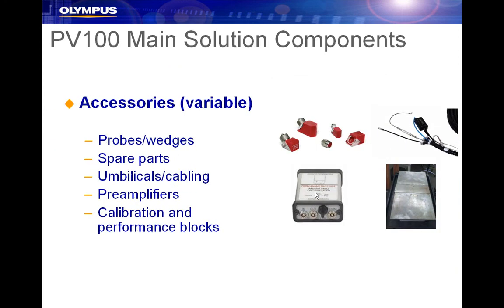Depending on the customer's needs, there are a lot of smaller components that typically go into a PV100 solution as well, including cabling, probes, wedges, spare parts, etc. All necessary components can be identified based on the welds to be inspected, so a total solution package is offered. If needs change, other accessories can be added later. Umbilical or divisible cable style wiring is typically used to group all the necessary inputs into one strand.